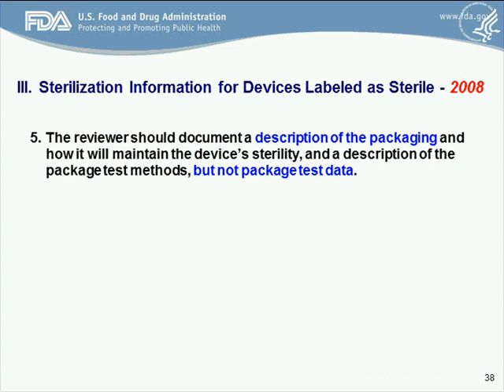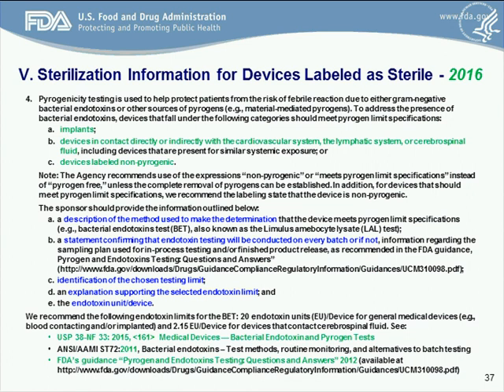An additional note — we received a lot of comment with regard to pyrogenicity testing. We had comments saying it was too prescriptive, and others saying it's a good thing because we're being more consistent with AAMI ST72, which is FDA recognized and calls for this information. Since that time, the other two references listed have all harmonized, so all four publications — including the current guidance — are harmonized on these issues.